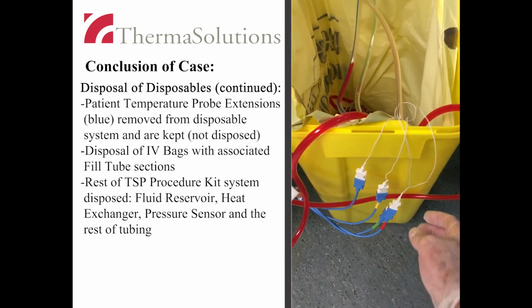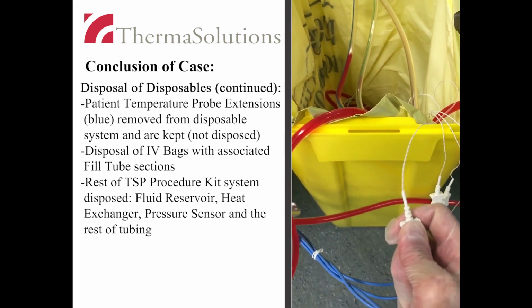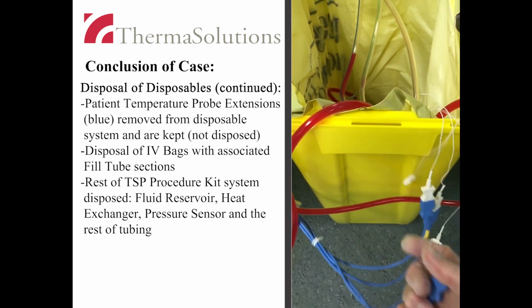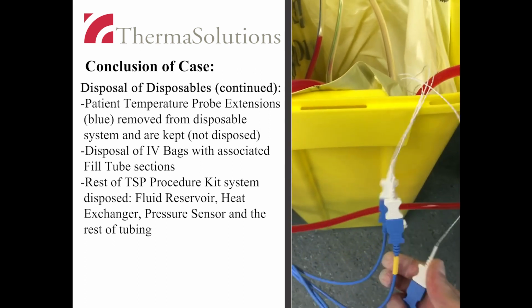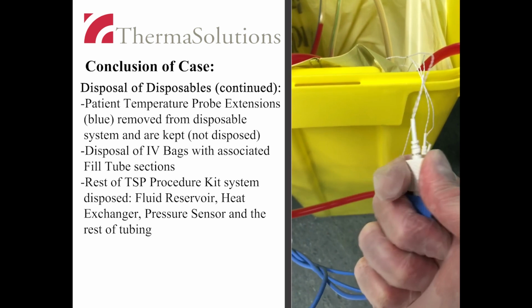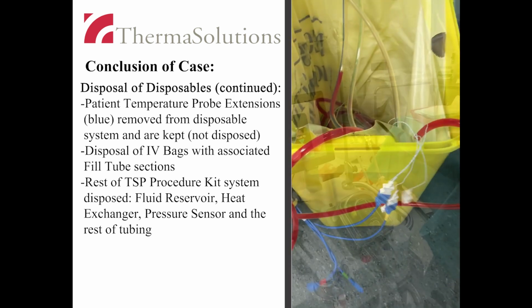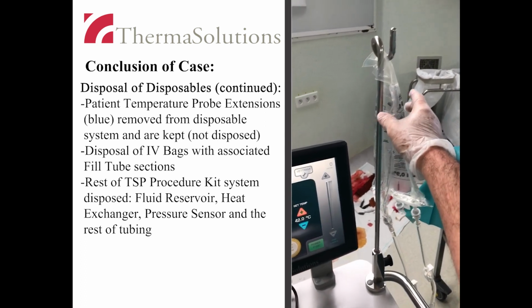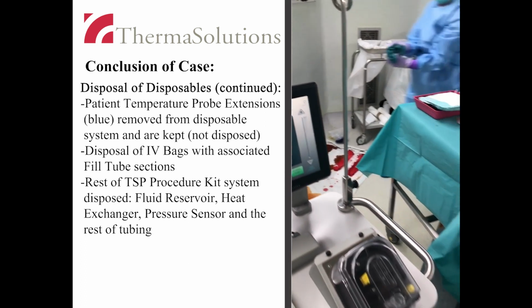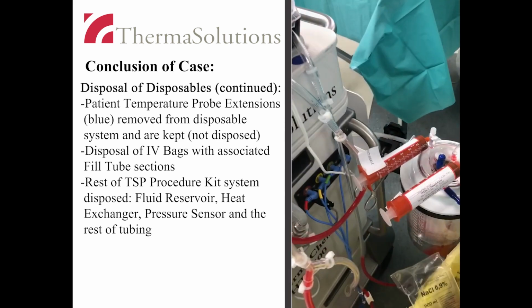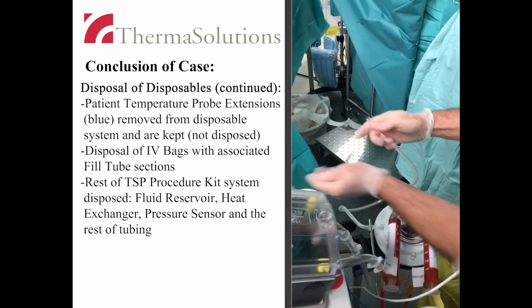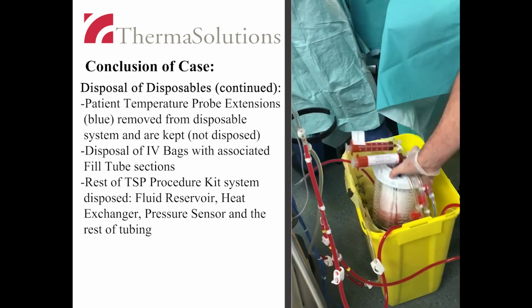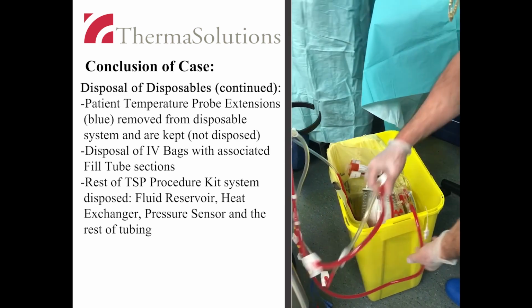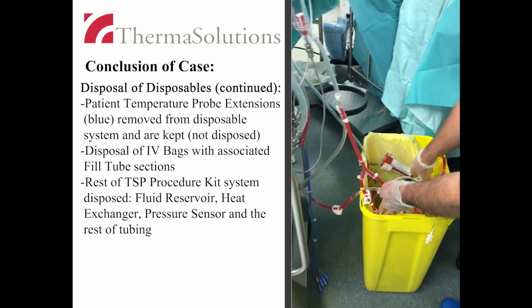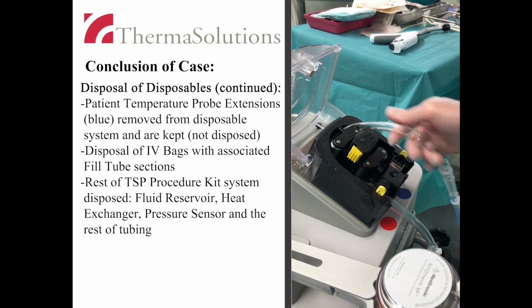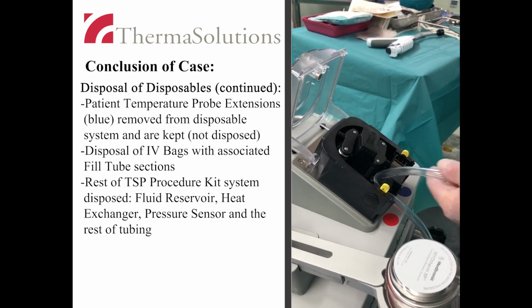The blue patient temperature probe extensions are detached and are kept for future use. The IV bags and the fill tube lines can be disposed with the TSP system. The fluid reservoir and the heat exchanger and associated tubing are all disposed of according to hospital procedure. The tubing is carefully removed from the roller pump.